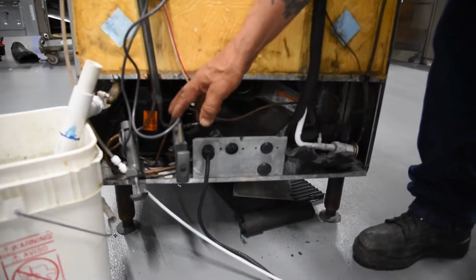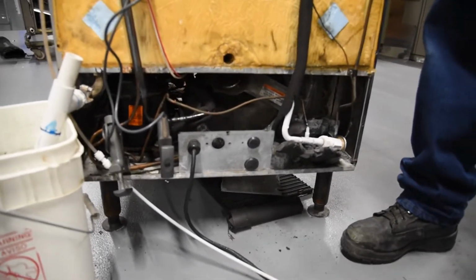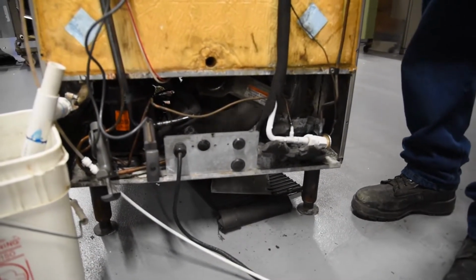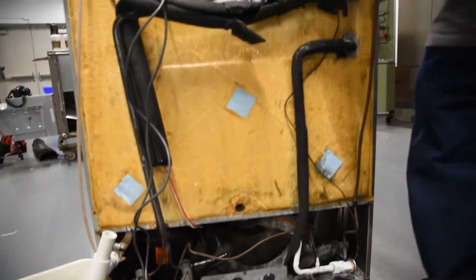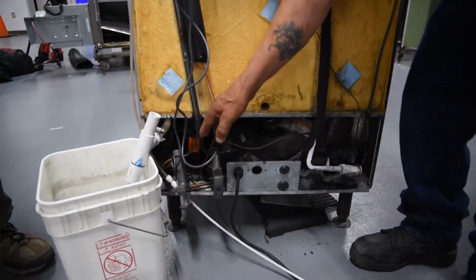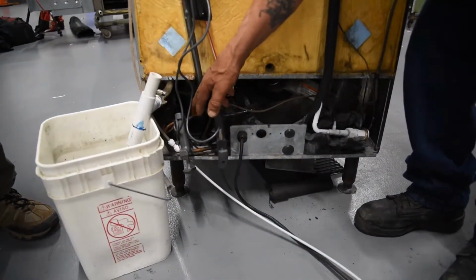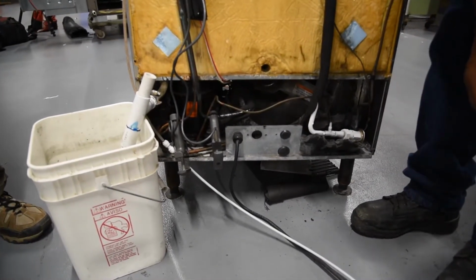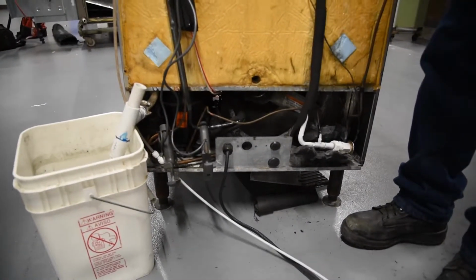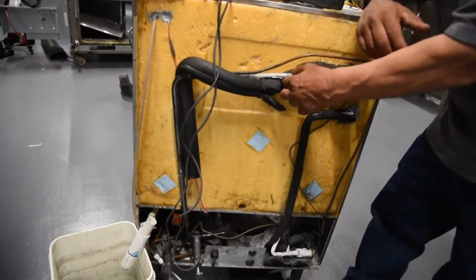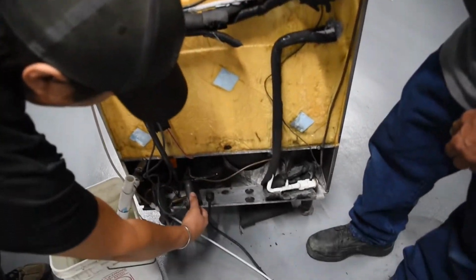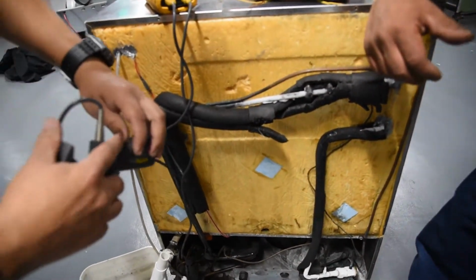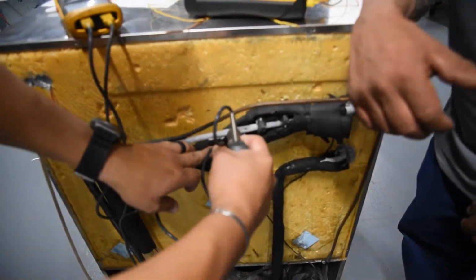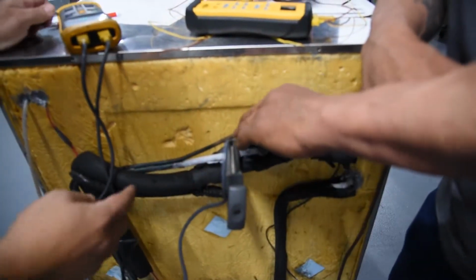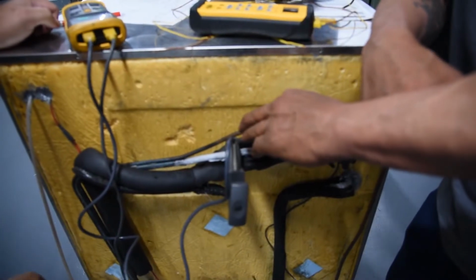Oh, I know why. You know why the superheat is so high? Right. Because we're absorbing heat out of the liquid line. Oh, because of the heat exchanger. Yep. So let's take the temperature here and see what happens. See how it isn't touching here? Right. So our temperature reading is being affected by the heat exchanger, so that's why we get a different temperature reading.